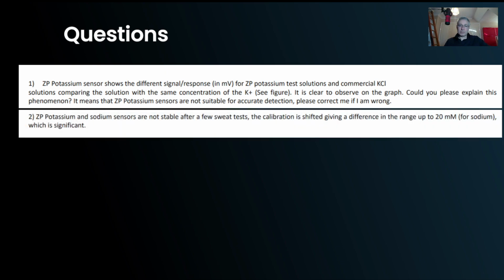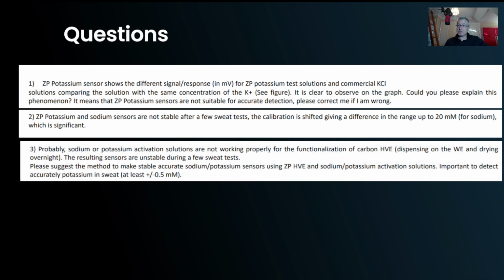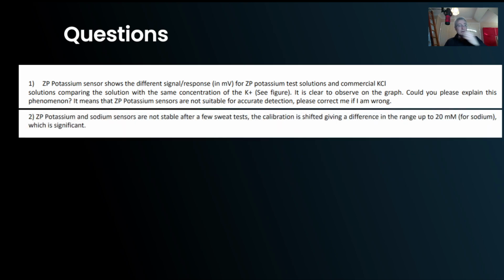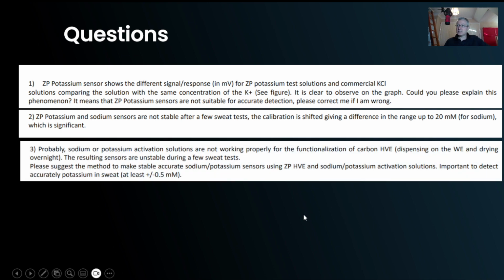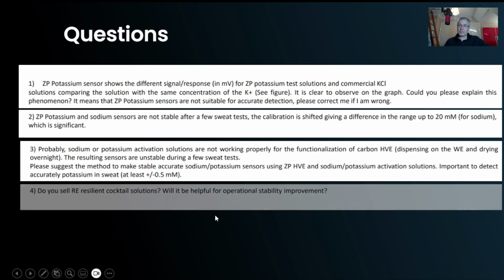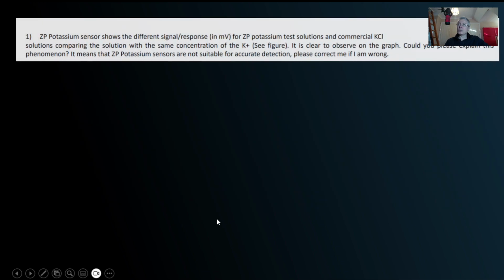Question number 1 is really, they've got different solutions. The sensor is actually showing fairly good linearity in both solutions, but there's actually a big offset variability. That offset variability is causing them concern about accuracy. But I honestly think that offset is due to the way you're testing, and you're not actually testing, I think, in the way that you're actually going to end up using these sensors. You probably already have a resolution able to resolve 0.5 millimolar, and yes, we do the cocktail mixture.